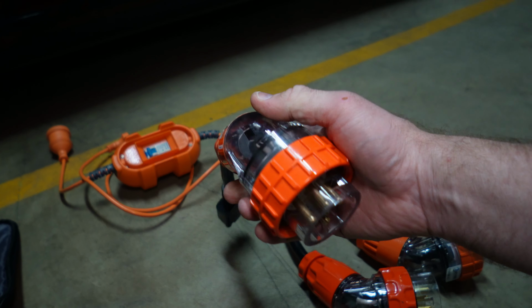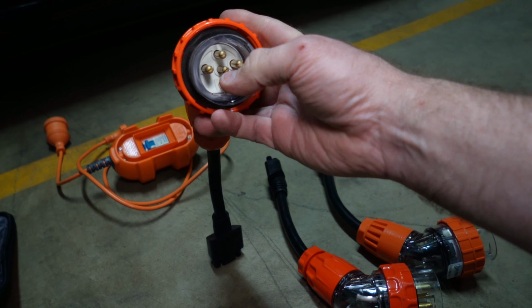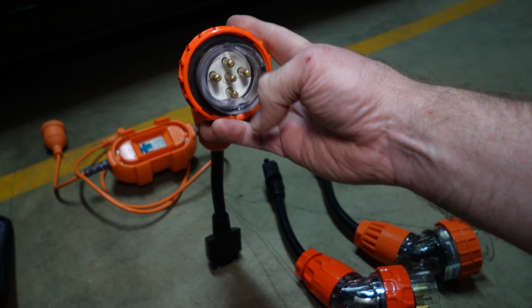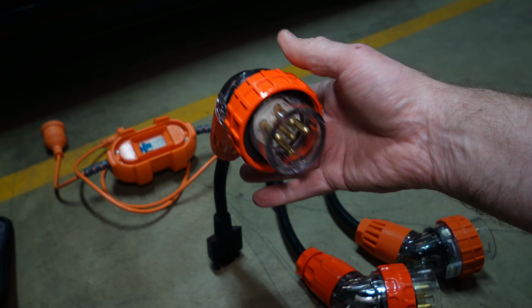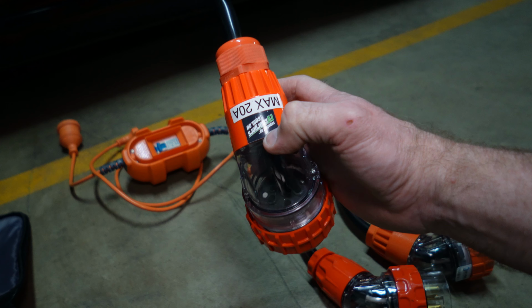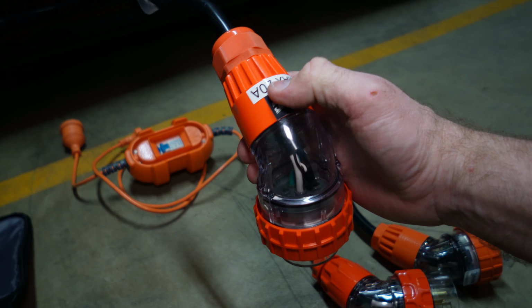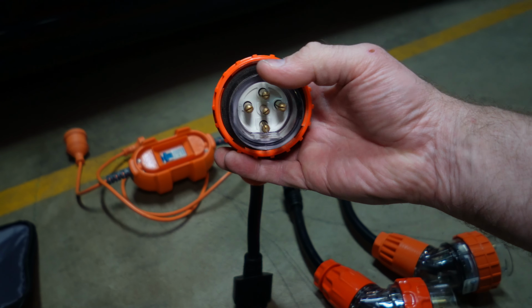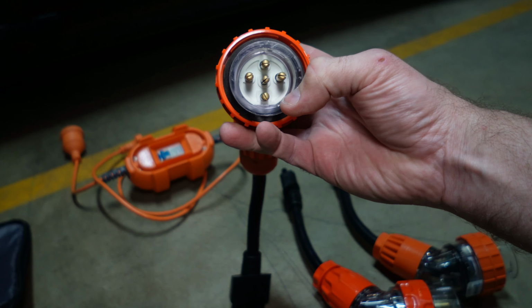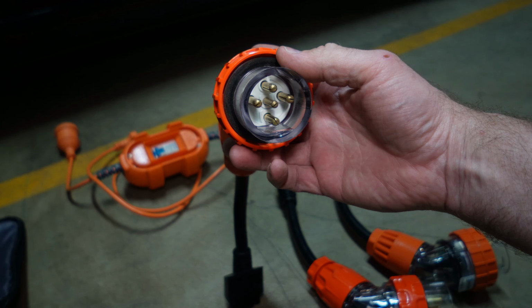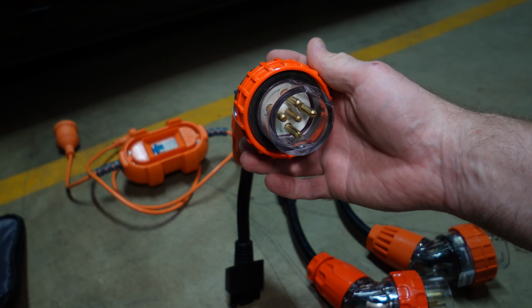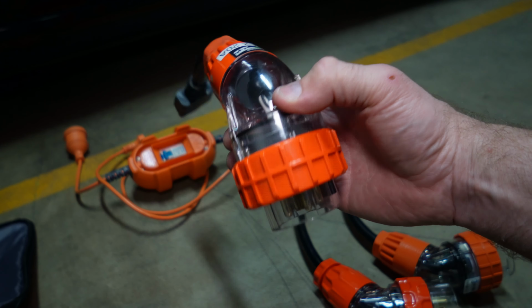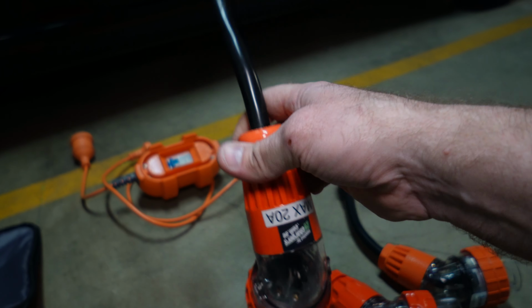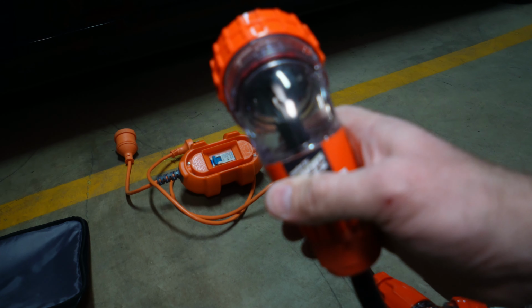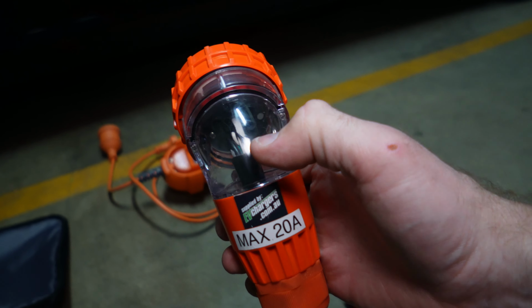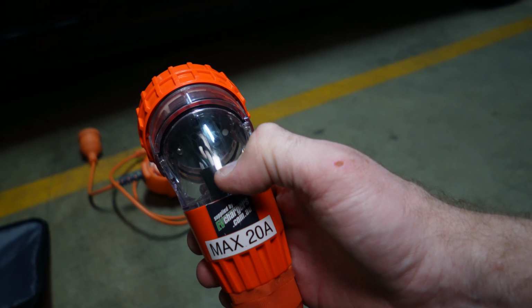So what they're doing with this 3-phase plug is they're only using one of the phases, so a 240 volt phase. This is designed for a 20 amp 3-phase plug, and the plugs themselves are different. This will only plug into a 20 amp receptacle wall plug, and you can see in the back here there is only 2 wires and an earth.